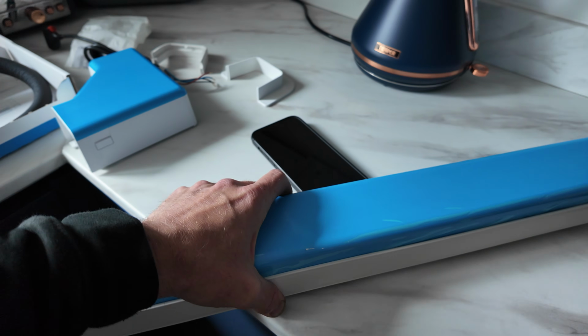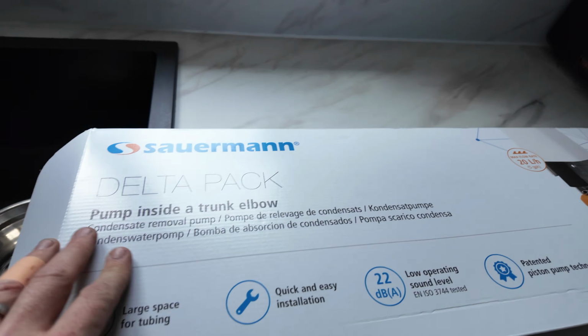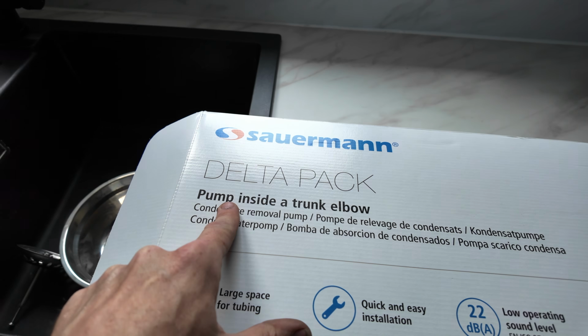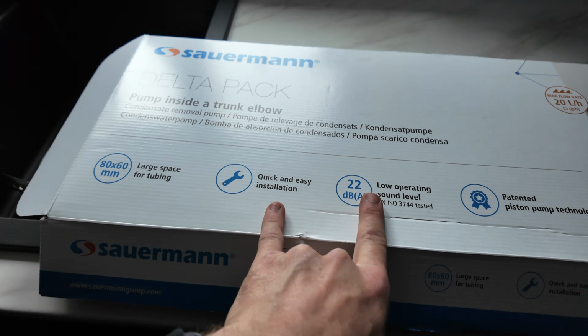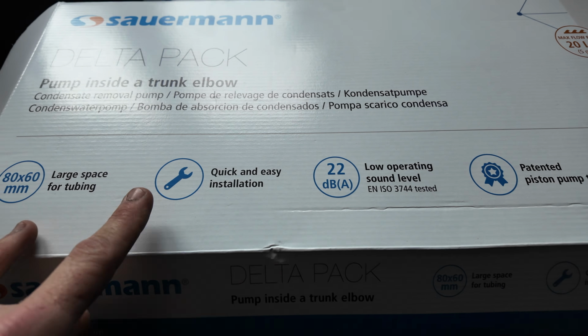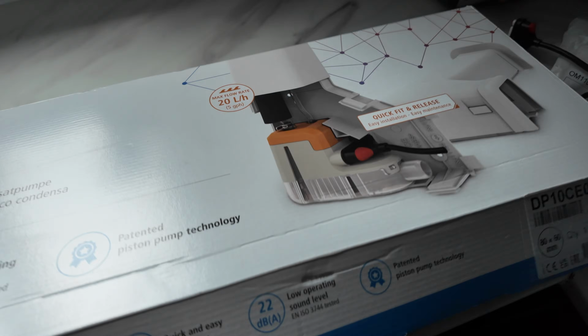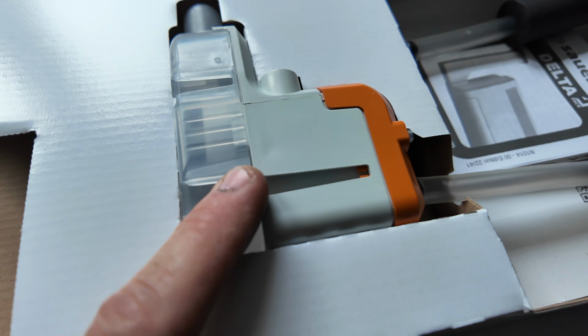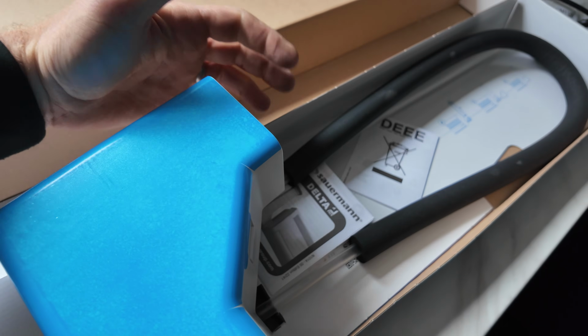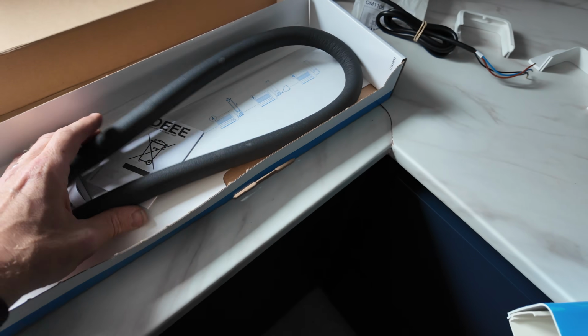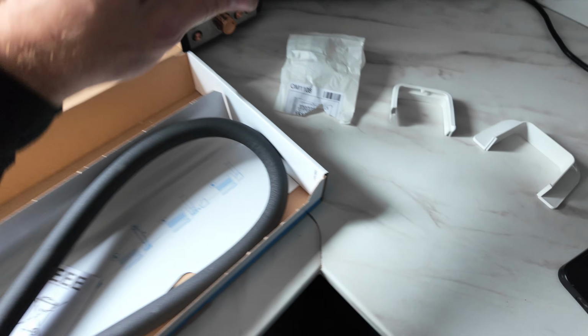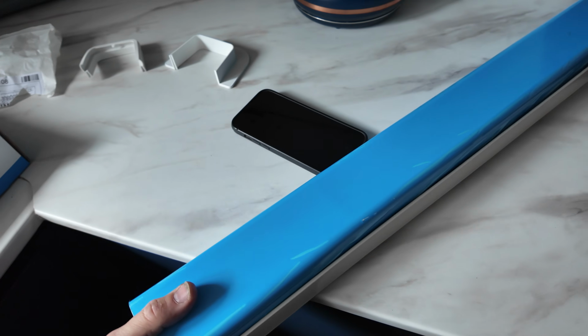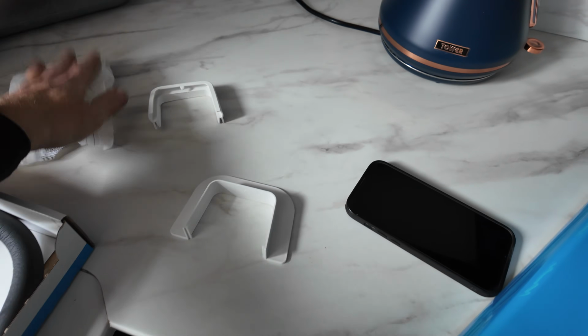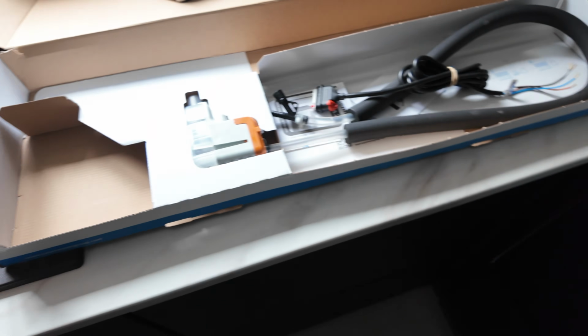So this is the condensate pump we're going to be fitting. I've just started unpacking it - it's a Sauermann Delta pack, so you get the pump inside a trunk elbow. It's got low operating sound, quick installation it says, but we're going to show you how to do that. There's the pump, which fits inside the elbow basically. Everything in this pack is there ready to go - you've got the electrics, I'll show you the wiring on that, the trunking, ceiling rolls, and fittings pack. So yeah, I'll show you how to fit that.